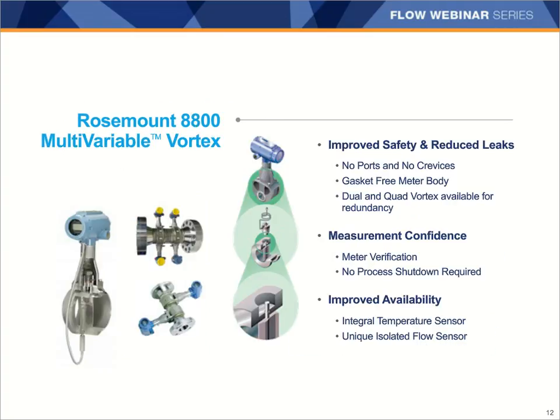Rosemount also offers an 8800 vortex meter that is used extensively for safety applications, and it has a lot of great attributes also. Some of the attributes that it has are reduced leak potential with a gasket-free design, meter verification that checks the electronics, and sensors that can be replaced without taking the meter out of service. The Rosemount vortex meter is also available as a dual vortex meter that basically eliminates the straight run needed for the second vortex meter, but it still provides two independent flow signals. These are great for safety applications.